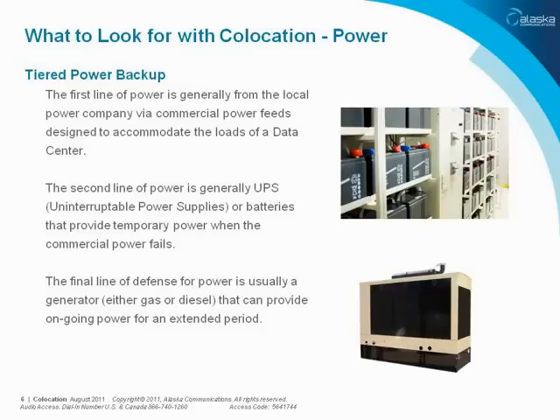Their purpose is to hold and provide smooth power to the data center while your final line of defense for a power outage comes into play, which is generally a generator. You're looking for redundancy in all these elements so that if one fails, others can carry the power, giving a smooth transition: commercial power, then UPS and batteries for the transitional power, and then the generators kick in if necessary.